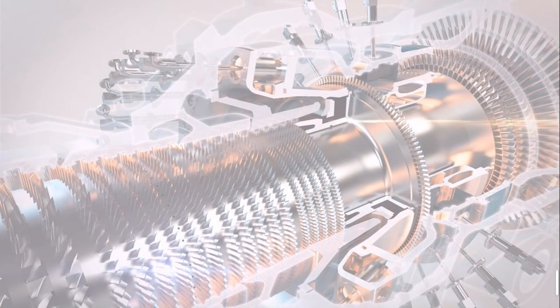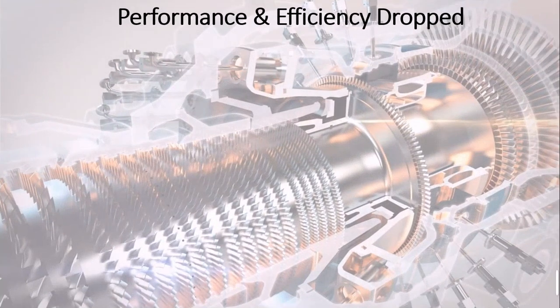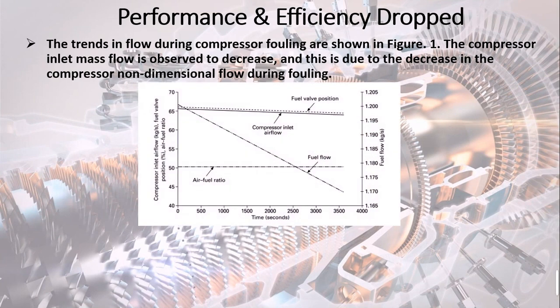Reason 1: Performance and efficiency drop. The trends in flow during compressor fouling are shown in the figure. The compressor inlet mass flow is observed to decrease, and this is due to the decrease in the compressor non-dimensional flow during fouling.